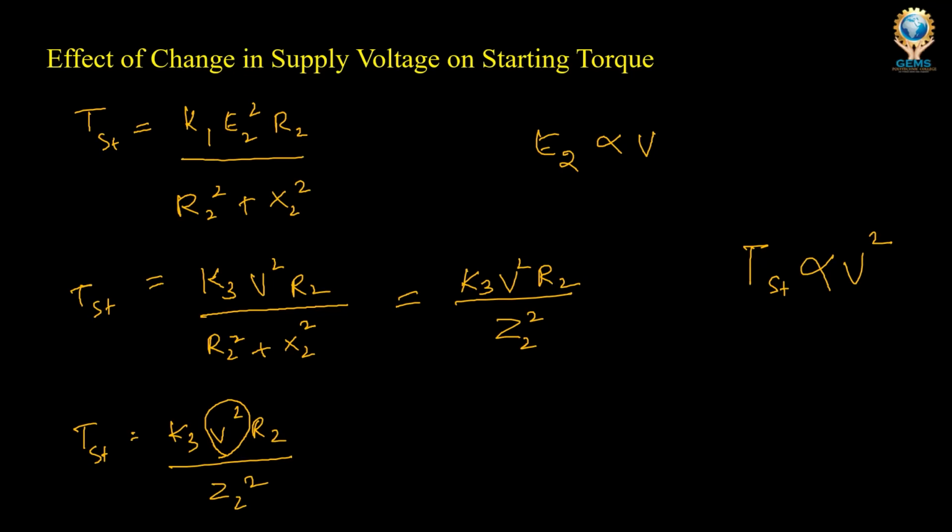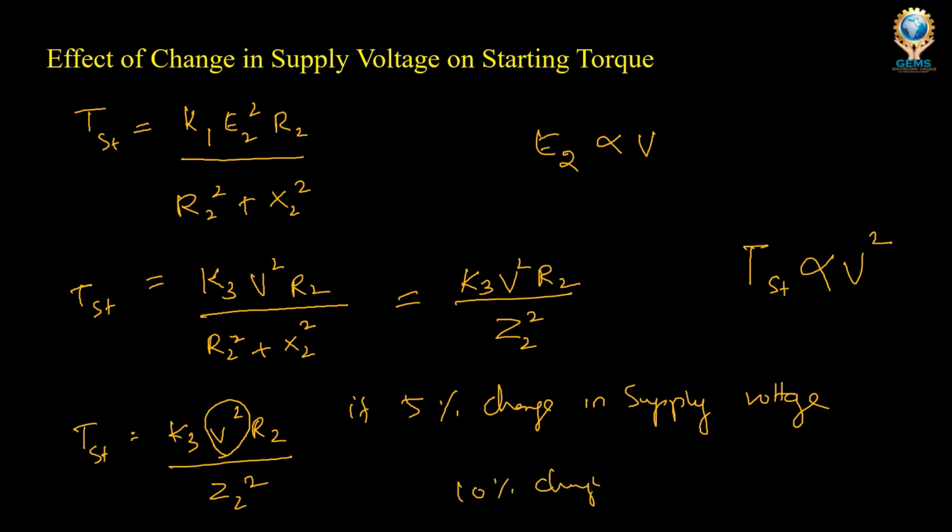Suppose there is a 5% change in supply voltage, there will be a 10% change in the torque. So this is the effect of change in the supply voltage on starting torque.